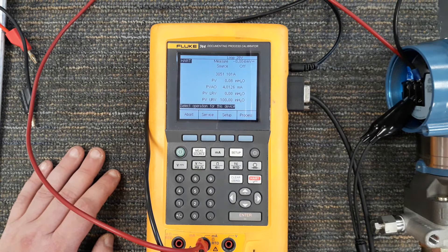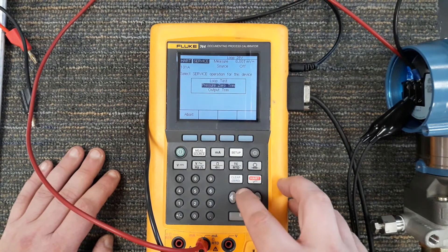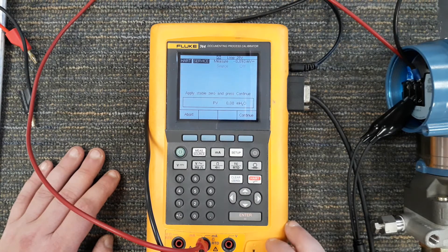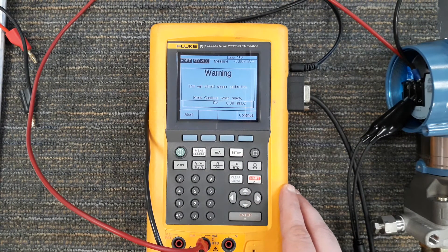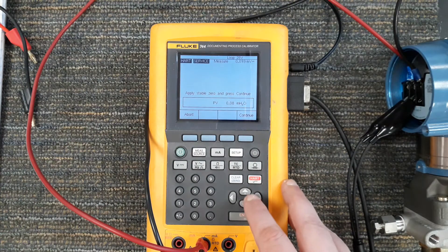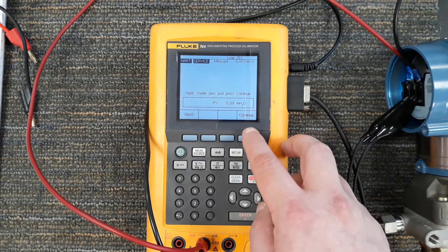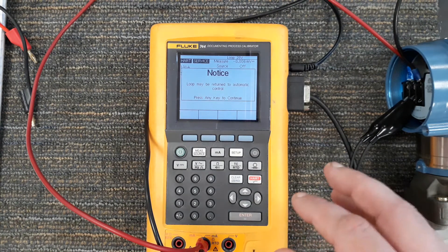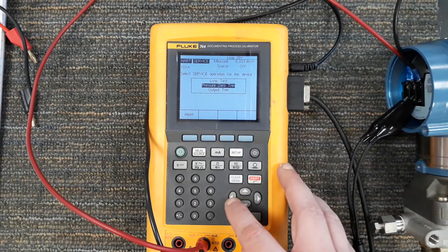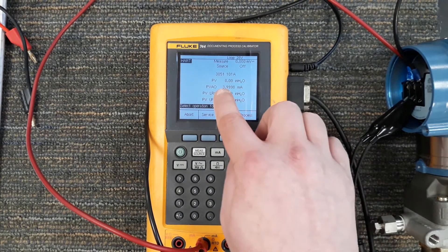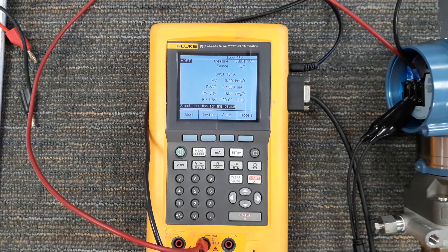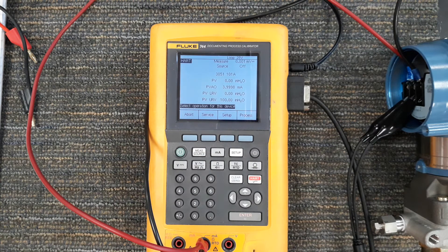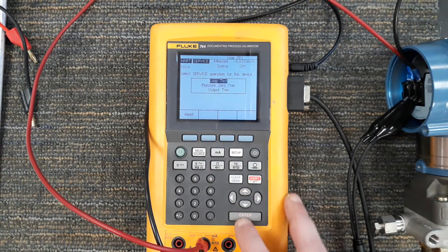I can hook up to this device and I could zero the transmitter. Right now the process variable, I'm going to hit done, I'm going to hit abort. It says process variable is 0.08. That's not that far off but that's not zero. It should be zero because the high side and the low side are both referencing the same pressure, so the differential pressure it's reading should be zero. That's something I would want to do a zero trim on. Under service, here we go, I can do a loop test, pressure zero trim. This will let me do my calibration of my pressure sensor. Now that 0.08, 0.09 should go to reading zero. I'm going to hit abort. Now I've got zero.